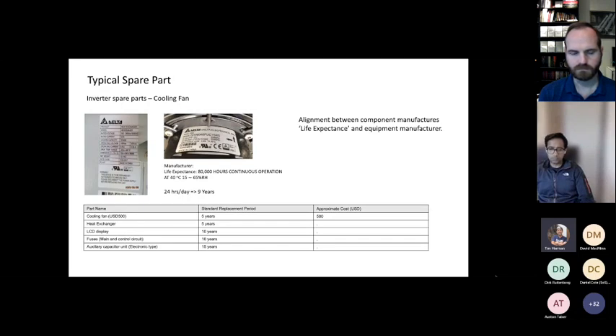Conditional maintenance and digitalization would mean that by collecting information about the temperature and any strange noises from that fan, and feeding it into my computer system, I can more accurately predict what's happening to that fan. I can also apply that across my whole fleet. So if I find this particular Delta fan is unreliable, I can step back, look at my whole fleet, and say I've got that fan installed in these other plants too — I need to watch that. Without this connection of information, a fan overheats and an inverter loses productivity in one location, and I can't necessarily predict where that will happen elsewhere. Having this digital information opens doors to predictive and condition-based maintenance, which is a far more effective and cost-effective way of maintaining a plant.